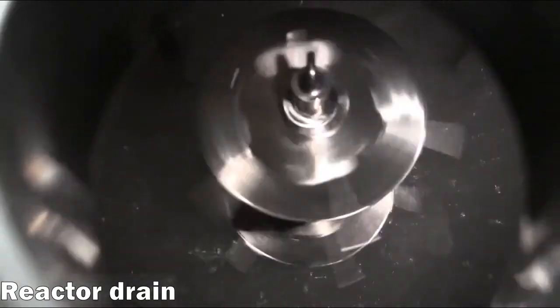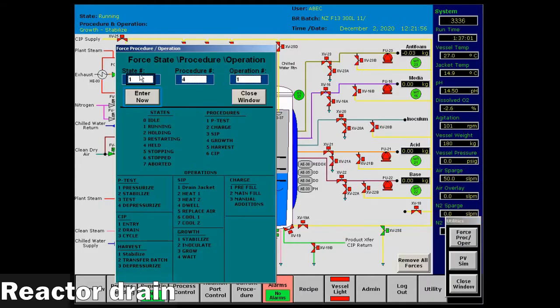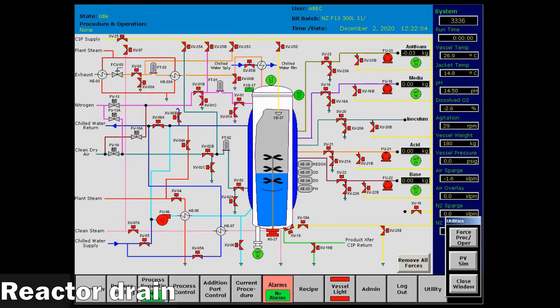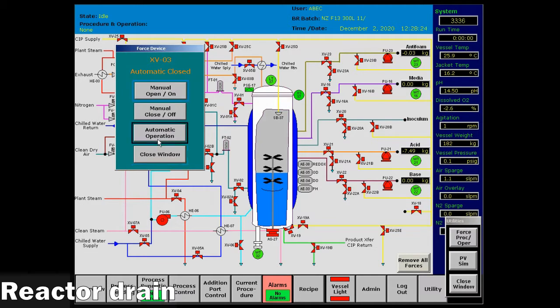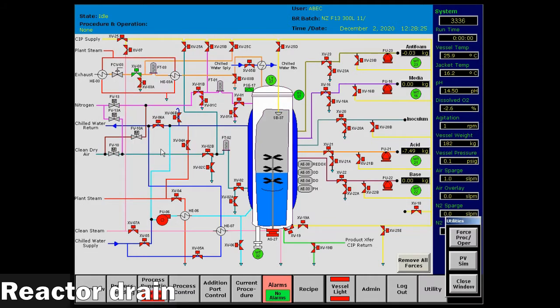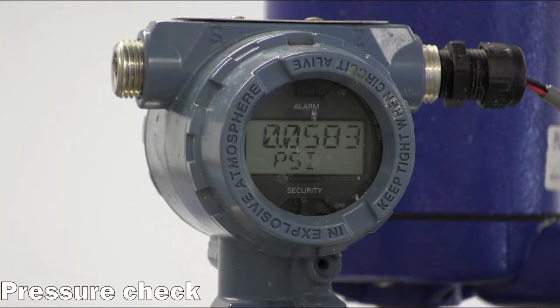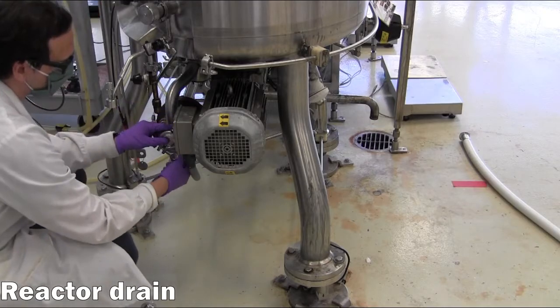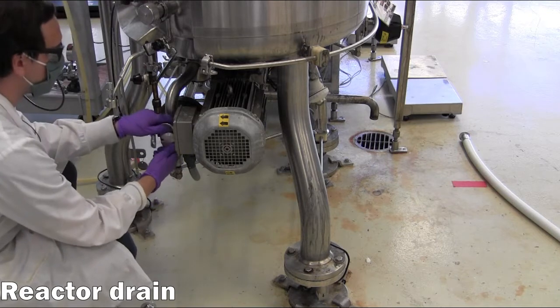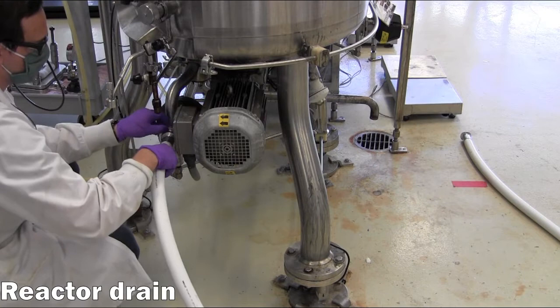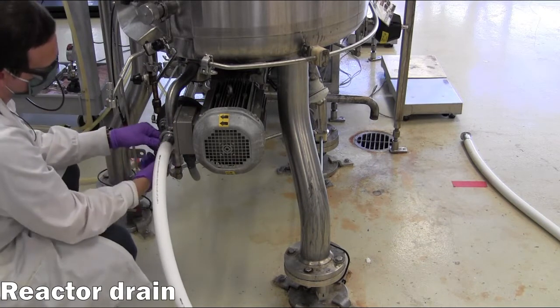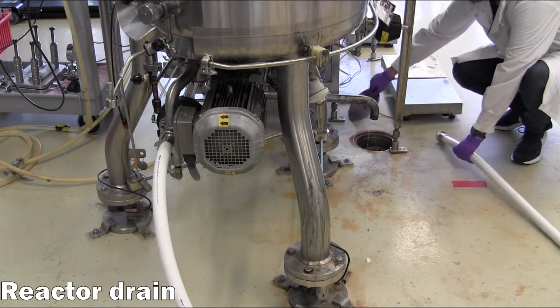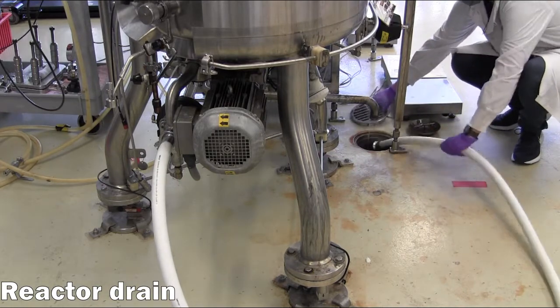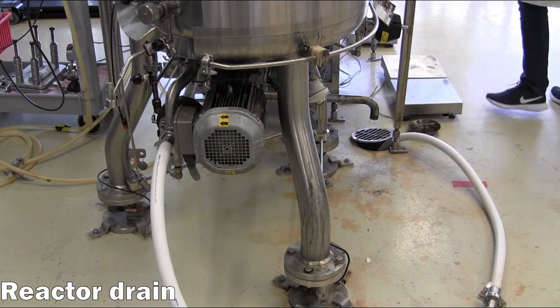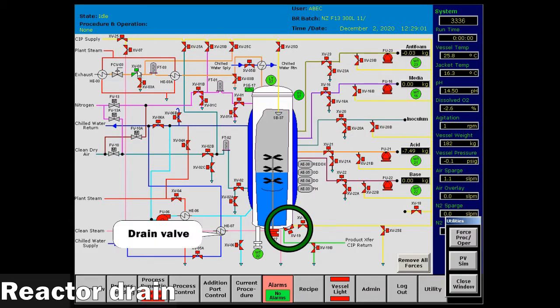The reactor must be drained before installing the probes. To drain the tank, put the reactor into idle mode and vent to take any residual pressure off of the vessel. Connect a hose to the 1.5-inch tri-clamp fitting at the harvest port XV19 and route the hose to a floor drain. Open the XV19 port on the control screen and wait for the water to drain.